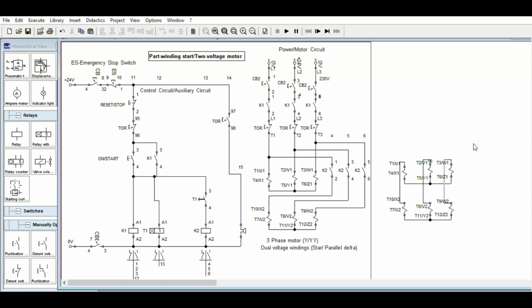In some cases, if you want to start this way using contactors, you place contacts here, here, and here. That means this one goes to the lines. You're going to break this one and place a contactor here, and also this one, because the first connection is series star. So place a contactor here and here.